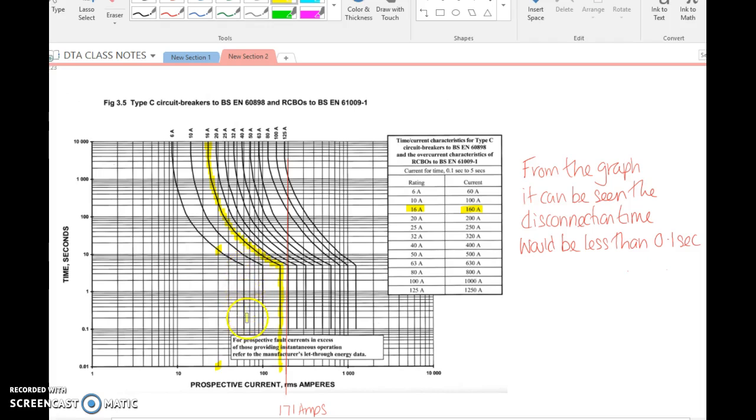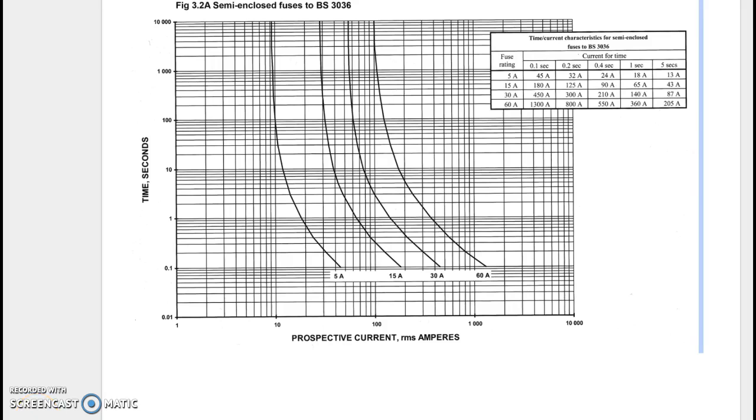On the subject of time current curves, we're going to look at the common curves on protective devices generally found in households and small commercial circuits. Starting with the old-school BS 3036 semi rewireable fuse wire, still in circulation today. There's not that many of them, a lot of installations have been upgraded over the years, but they are still out there and recognized as a British standard protective device if they've got the right size fuse wire in.